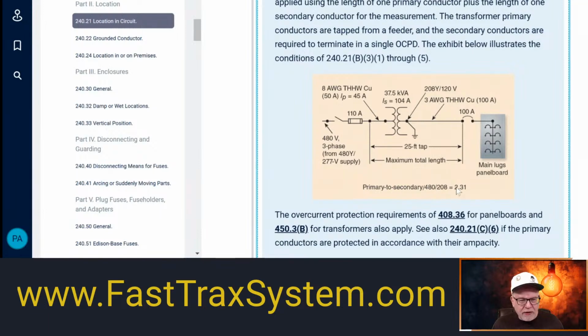And there's our primary to secondary voltage ratio math we did a minute ago, 2.31. And this happens to be a 480 volt three-phase system, okay? And here's 110 amps on the primary side, and this transformer is tapping a feeder, okay? In this scenario right here. All right, so this happens to be a 37.5 kVA transformer. It looks like it's going to be 104 amps in this scenario. So let me do that math real quick. Let's do 37.5.